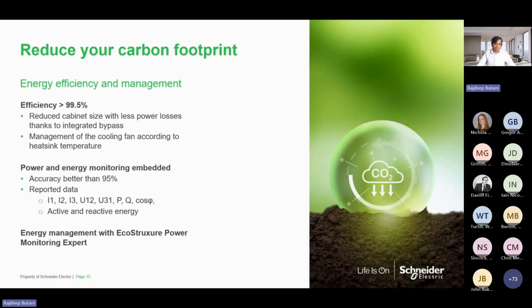It's in the same direction when we talk about carbon footprint - there's no lower efficiency even as we reduce carbon footprint. It's still 99.5% efficient. It also comes with power and energy monitoring management, where you get all the data of the drive, so you don't need an extra power monitoring tool to understand how much your drive or motor is consuming. You get data on line current, line voltage, efficiency, and active and reactive power as well.